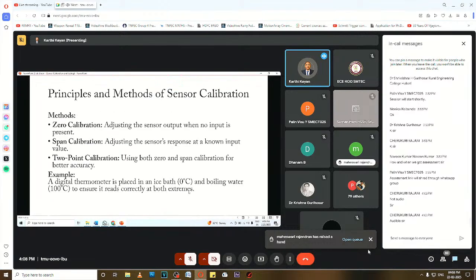Next, principles and methods of sensor calibration. What methods are used in sensor calibration? First one is zero calibration. Second one is span calibration. Third one is two-point calibration. Zero calibration means adjusting the sensor output when no input is present. Span calibration means adjusting the sensor's response at a known input value. Two-point calibration uses both zero and span calibration, for example 0°C and 100°C, to ensure it reads correctly at both extremes.